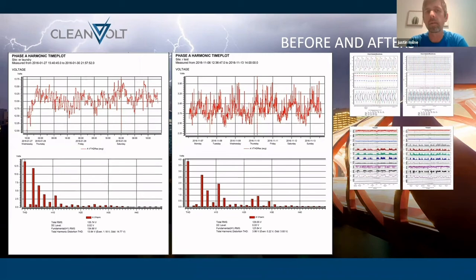The last studies that I wanted to share on this same particular reading were harmonic time plots for this study. We found that in the before test, we had the third order of harmonic on phase A, almost up to 12.5 volts. We found this interesting because, being a laundromat and given the type of equipment that is present here, the third order of harmonic should not even be present in this situation.